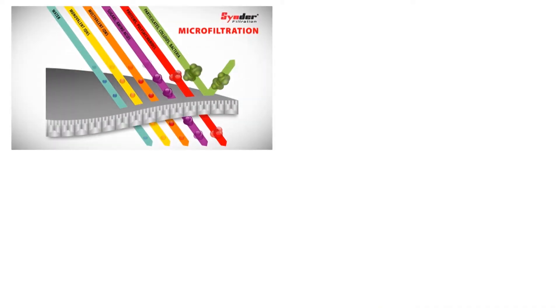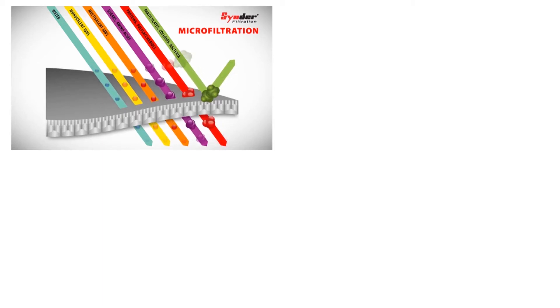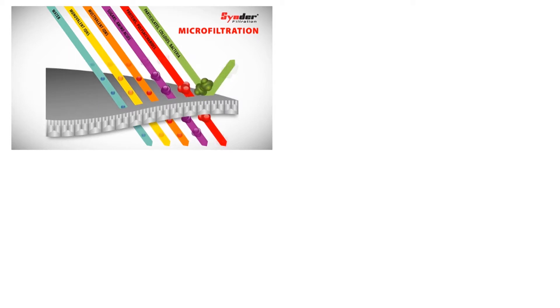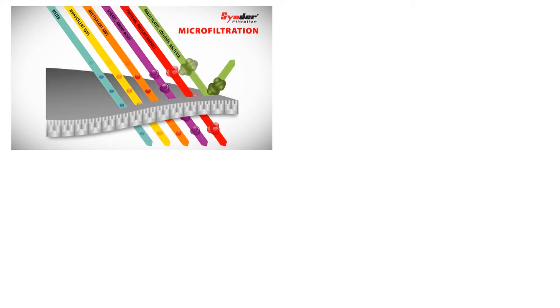We're going to be talking about three different treatment processes in this lesson, the first being membrane filtration. Under the membrane filtration lesson, we're going to be talking about microfiltration. The microfiltration membranes reject particles as small as 0.03 microns, as compared to a multimedia filter which can filter out particles as small as one micron. Microfiltration is used in some applications in place of the mixed-media gravity filters.